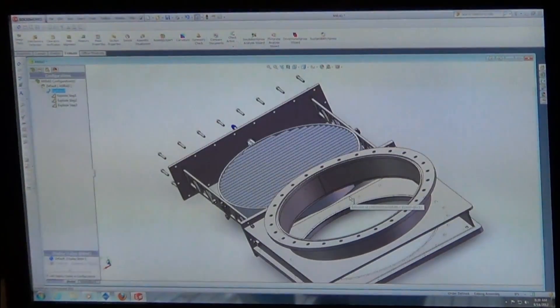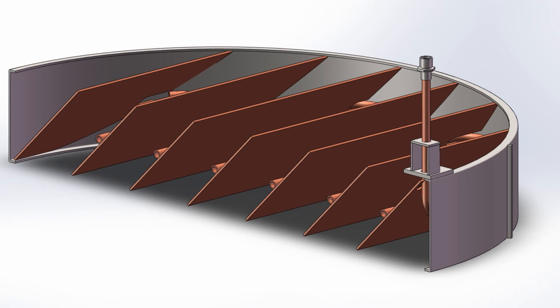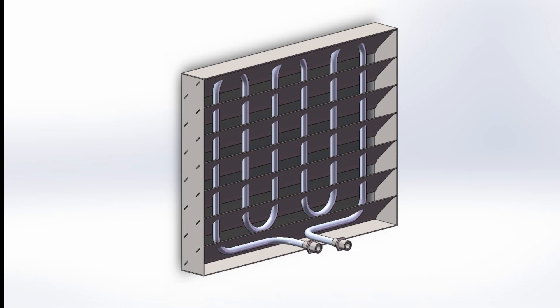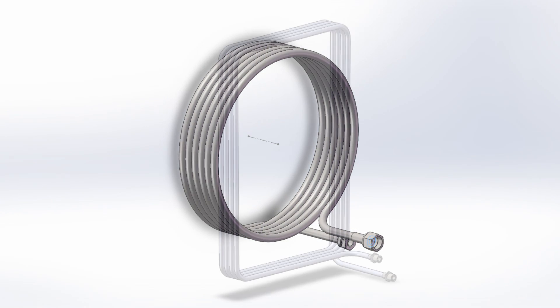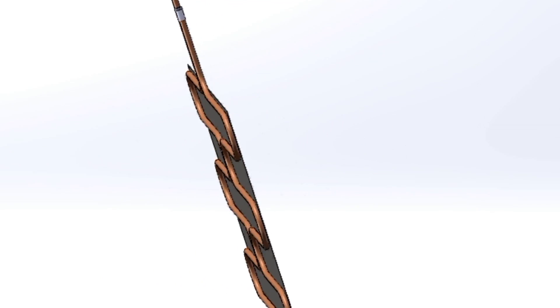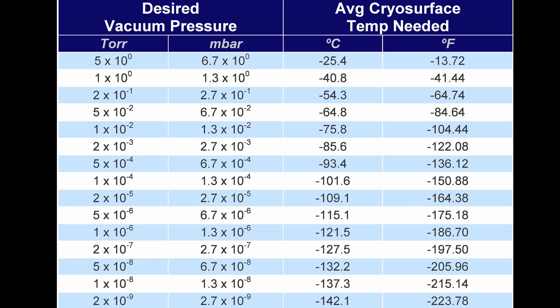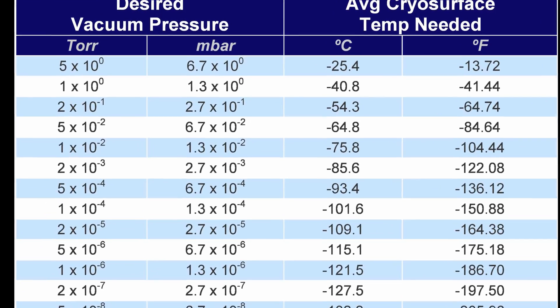Another style is the line-of-sight blocking louver-style baffle, which allows greater conductance while stopping 90% of contaminants. Other options are rings and coils, which are not optically dense. Cryo coils, often called Meissner coils, consist of tubing that is often brazed to a backing plate with a large surface area. These pull moisture from the air and greatly increase pumping speeds — the colder the surface and the larger the area, the faster the pump-down time.